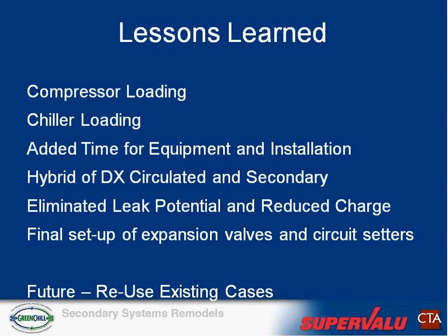One of the things, of course, we'd like to say we did everything perfect right from the very beginning, and as good as Rob's people are and the construction people are, one of the things that led us to some of the extra refrigerant leaks we had in the first store was we didn't really address the existing gasketing on receivers and filter canisters, liquid side and suction side filter canisters, the pressure controls - all that was existing and remained pretty much existing. All we did was essentially shorten the piping from circuiting all the way out onto the sales floor, to an evaporator case, over to the pump skid, to the liquid plate heat exchanger.